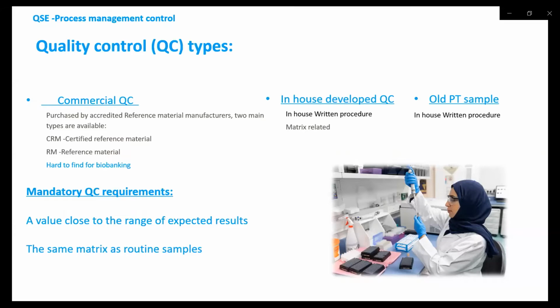There is something called in-house developed QC. We can develop our own QCs, and the only thing is that we have to write them down, and of course we have to monitor them, we have to test them, and then later we have to monitor them. It's important that the in-house QC, as any other QC, will comply with the two mandatory requirements: that the value will be close to the range of expected results, so we will not compare pears to apples, and that we will compare the same matrix. For example, DNA from saliva or DNA from whole blood can have some differences. That's why it's important to closely specify what kind of matrix we are going to use.